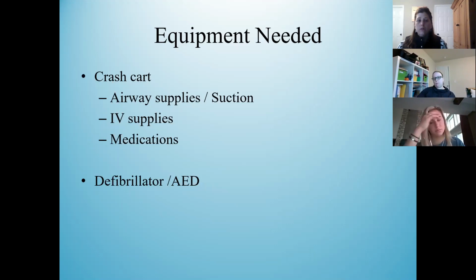Now with the defibrillator or the AED and the suction machine that sit on top of the cart, those are also typically put through a test at least once a 24-hour period, but sometimes once a shift. So it might be done with the day shift and the night shift, since most of our places work 12-hour shifts. So there's basically a way just to test it. You turn it on. You'll learn that during your orientation, and it basically does an internal check to make sure that it's ready to deliver a shock should one be needed.